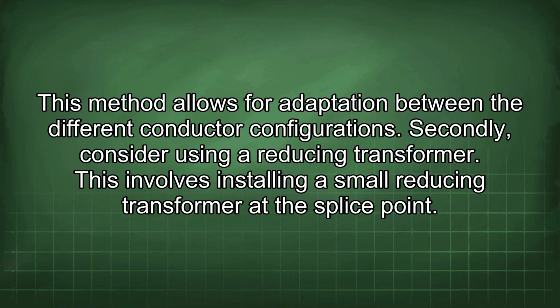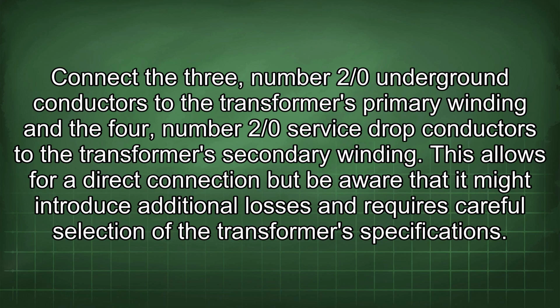Secondly, consider using a reducing transformer. This involves installing a small reducing transformer at the splice point. Connect the 3 2/0 underground conductors to the transformer's primary winding and the 4 2/0 service drop conductors to the transformer's secondary winding. This allows for a direct connection, but be aware that it might introduce additional losses and requires careful selection of the transformer's specifications.